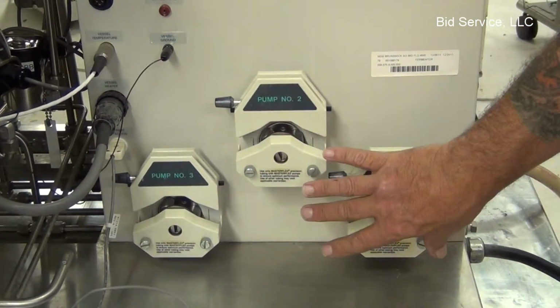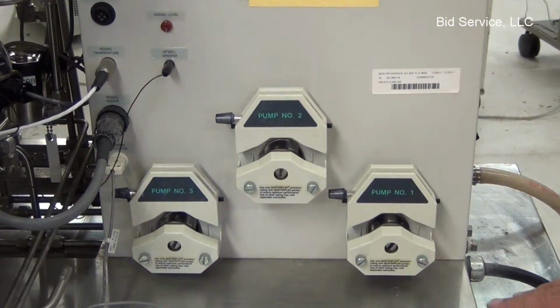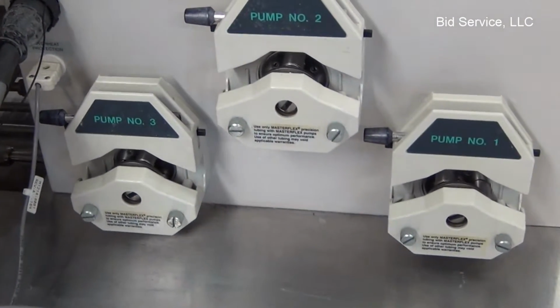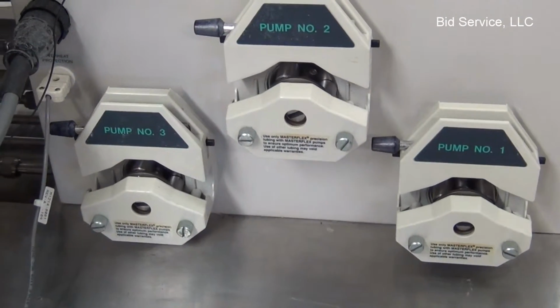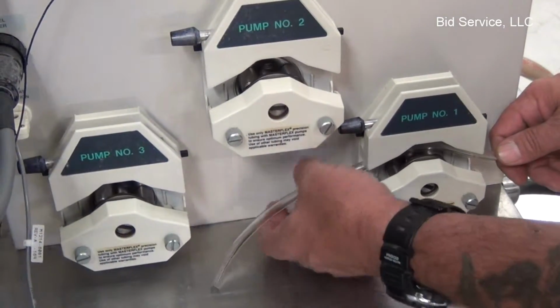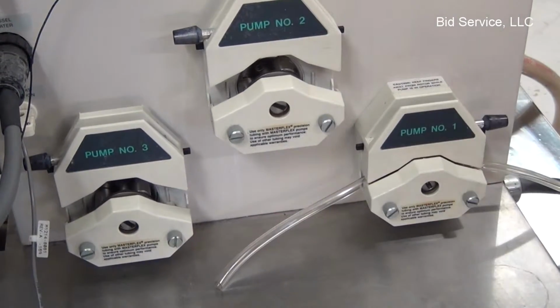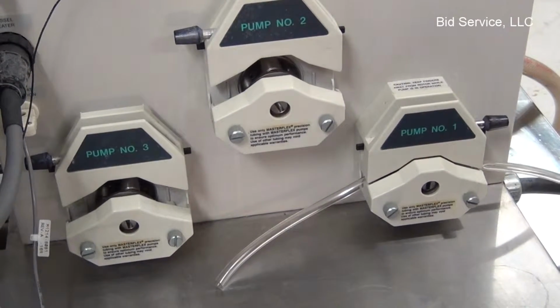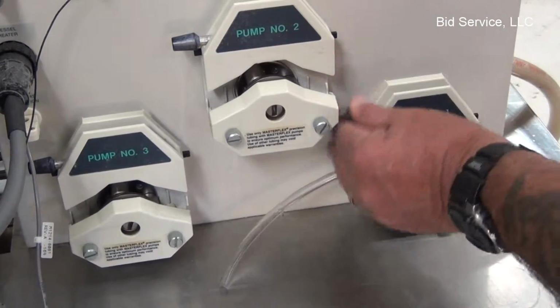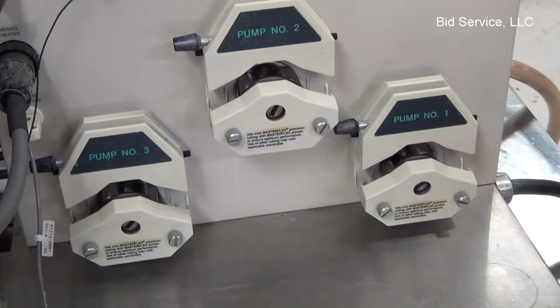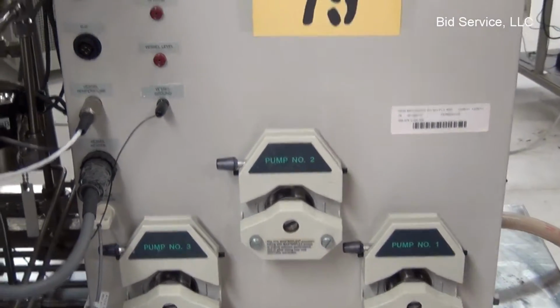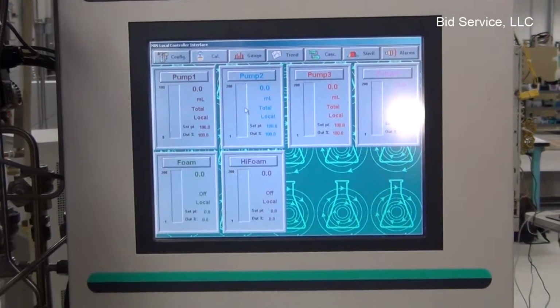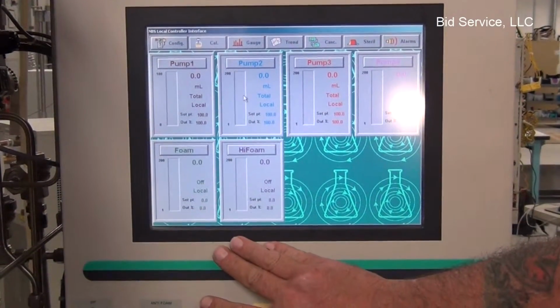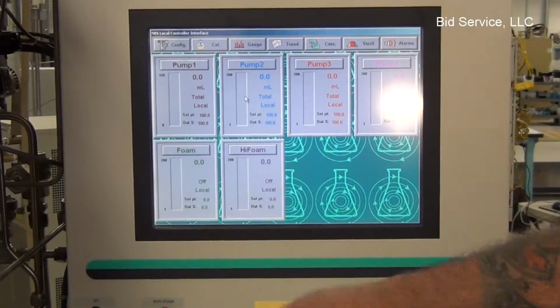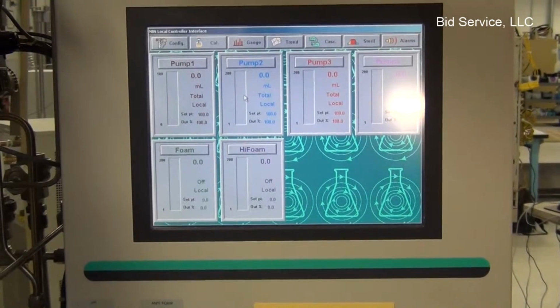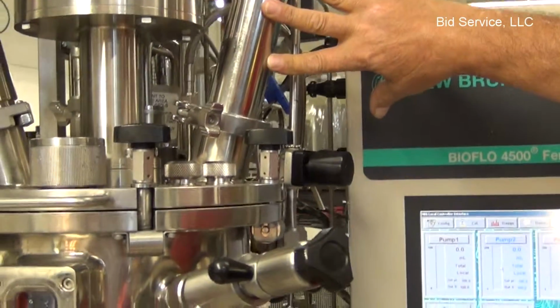The way this works is it's a peristaltic pump which uses tubing to go through here. So you would take your tubing, feed it in like that, and then lower that down, and it would pull whatever you're putting in there, acid, base, whatever, into the system. What determines the flow is the diameter of the tubing and the viscosity of what you're pumping. Pump number 4 up here is an external pump control. There is no pump on the system as designed. And here's your foam and high foam. That is also an option not included on the system. However, the foam control mechanism is present, and it's located up here.